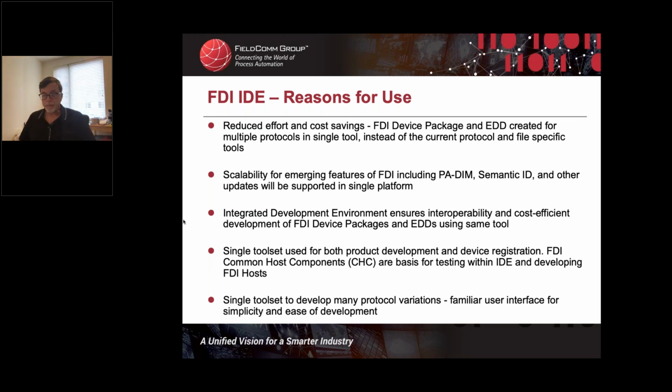So this FDI-IDE is our future for maintenance of the tools necessary to build both DDs and FDI packages and any other technologies that we see in the future. So with an IDE as being a single IDE tool set, it creates a platform where you're testing on the same tooling that host systems can use for development of their hosts. So the common host components are used to build this IDE platform through the reference runtime engine, which is a reference host used for testing of the packages and the DDs once they're built in the IDE.